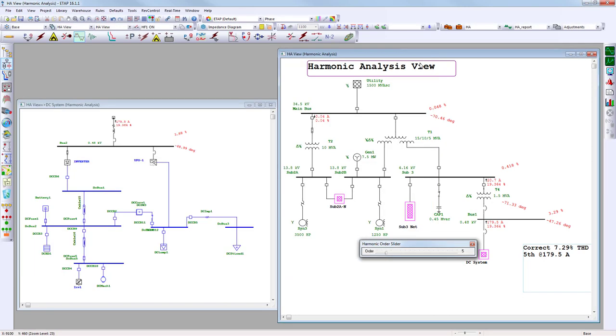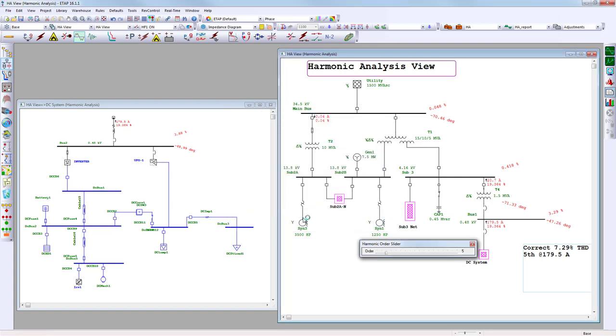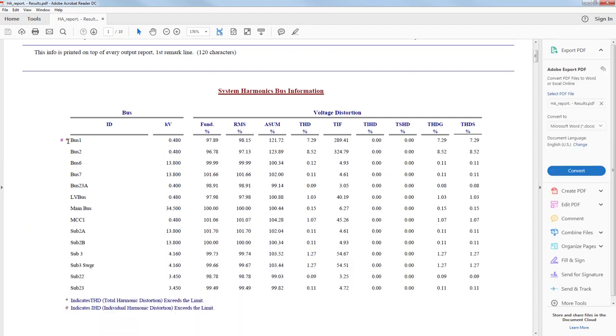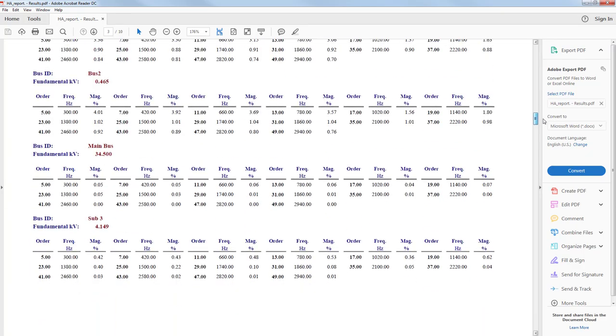After recording harmonic results on the one-line diagram, you can also print the report to have all information at hand. Opening the report from the right-hand side under Results, output to PDF format — you see the complete report not just for bus 1 but for every location. You have your fundamental column and total harmonic distortion with various indices. Important: a hashtag or star symbol quickly indicates when a location has exceeded its limits. Bus number one shows this alert.